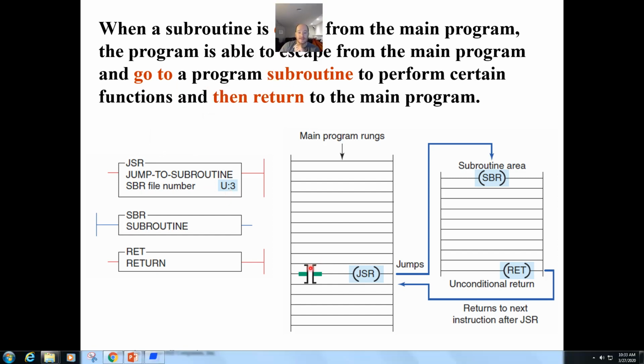So when this instruction is false, it will completely ignore this. But the way that I like to think of a subroutine is when it is active, or if there's not an input in there, you're basically taking these lines right here and shoving them in between these lines right here. So if it's 5 rungs, it's like adding 5 rungs into it whenever this is true, or if there's no input there and it's always true, it will run through.